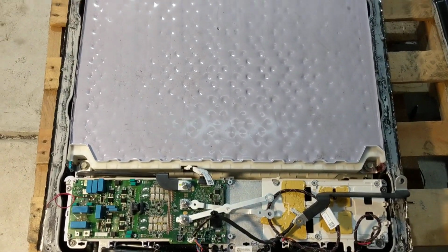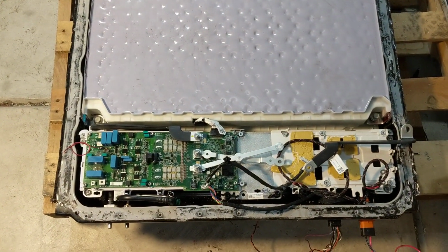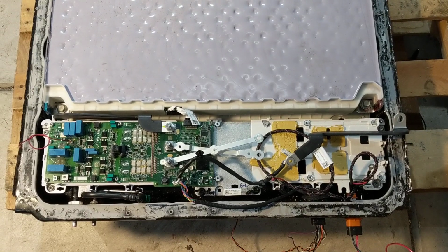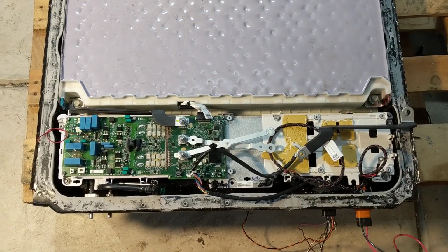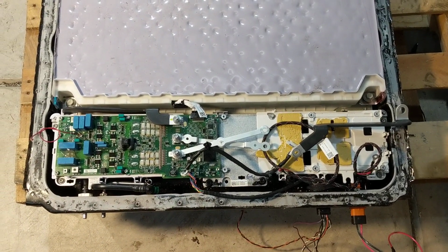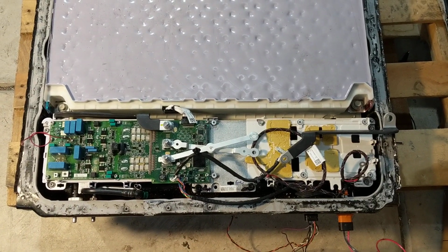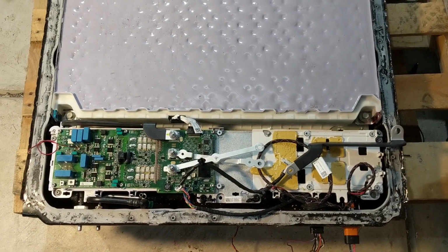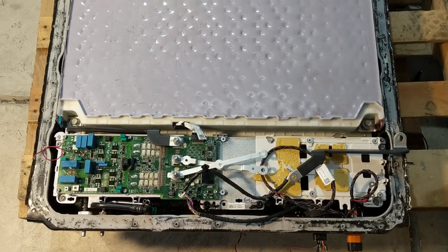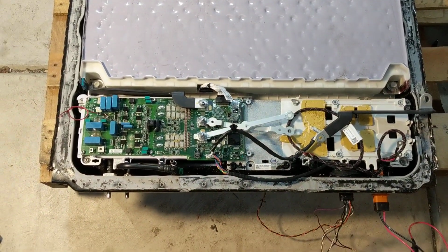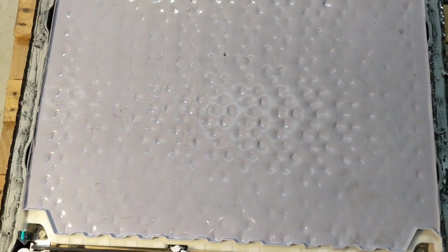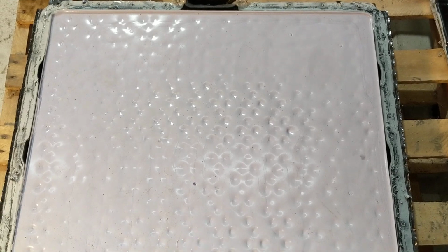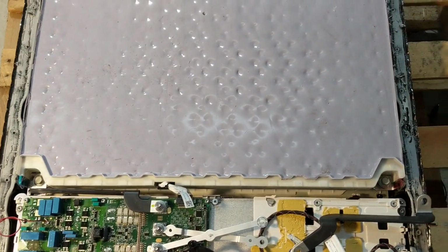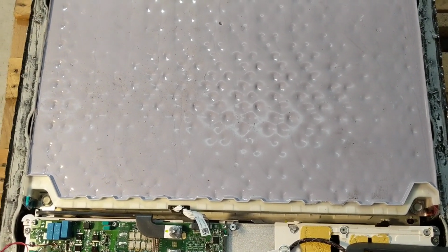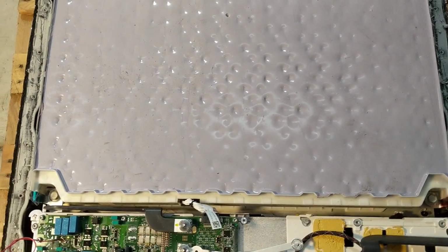What you're looking at is one of 16 modules out of a Tesla Powerpack. I believe this is the Powerpack 2.5, so not their completely latest revision, but pretty up there. This is very similar in construction to the home Powerwall, except there are 16 of these modules that make one cabinet, and in a lot of installations they use at least probably 4 cabinets to complete the install. What we have here is the same battery construction you'd find in a Model 3 module, but it's one big module. This is basically 48 volts, or 12 series strings of lithium batteries put together.